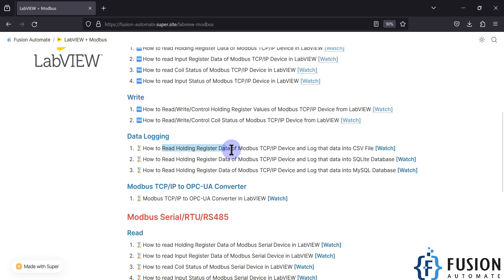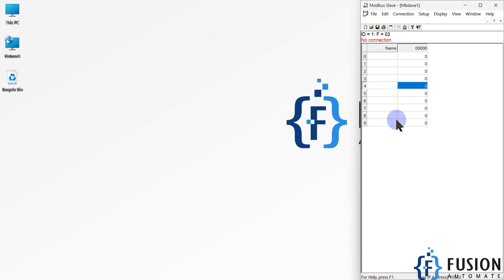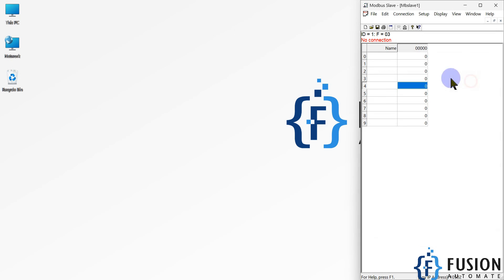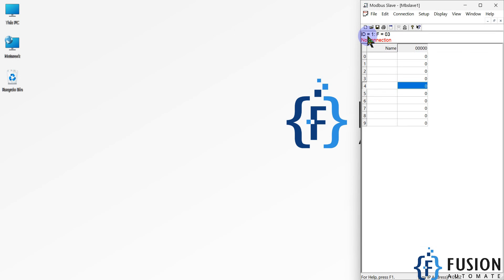We are going to read the holding register data of our Modbus TCP/IP device and log that data into a CSV file using LabVIEW. Here is my Modbus simulator — Modbus slave software. I'll go to Setup, then Slave Definition, and select the holding register because I want to log the holding register data. Slave ID is 1, function code 3 for holding register.